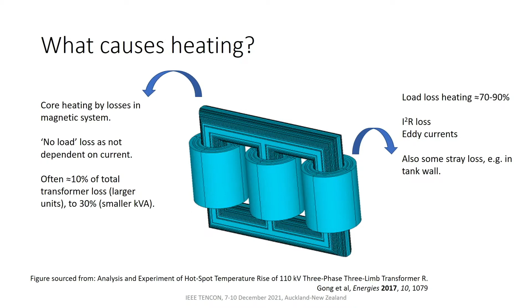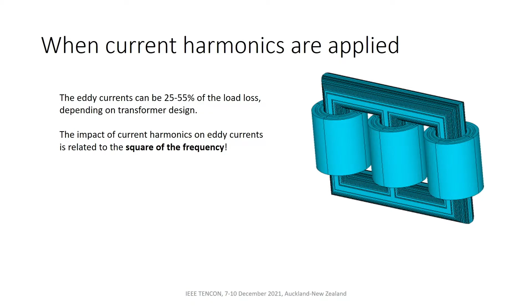Now, if we take current harmonics coming from DC devices entering our system, we're quite interested in these eddy currents, which can be anywhere up to half of the load loss. It does depend on the design again. The relative impact of a current harmonic on these eddy currents is related to the square of the frequency. So it's not just the actual load, but also the frequency of those currents. If we look at higher frequency harmonics due to something like an inverter, we can ask what it is actually doing to the transformer temperature.